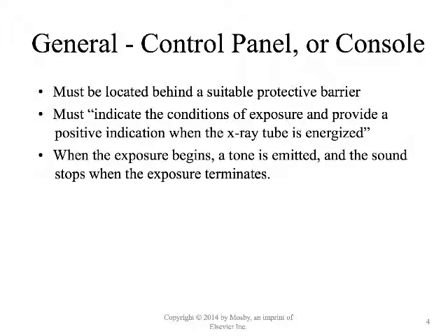Guess what? If the light is not lighting up or the beep is not beeping, it is your job to make that thing light up or to make the beep beep, or to say that we can't use this machine right now. That is your job. That is clearly within your scope of practice. But I can't tell you how many X-ray rooms I've seen that don't light up when we're making an exposure.